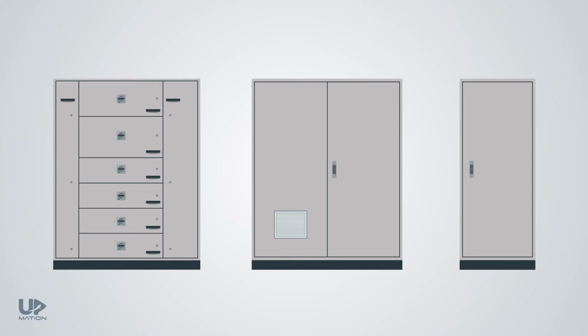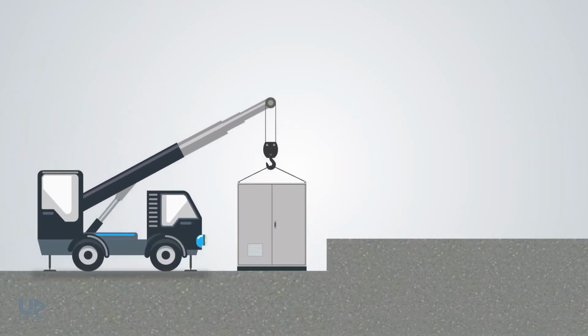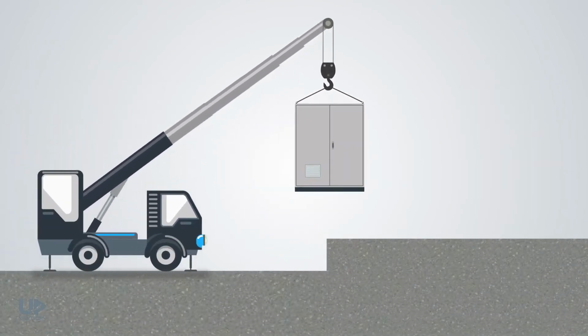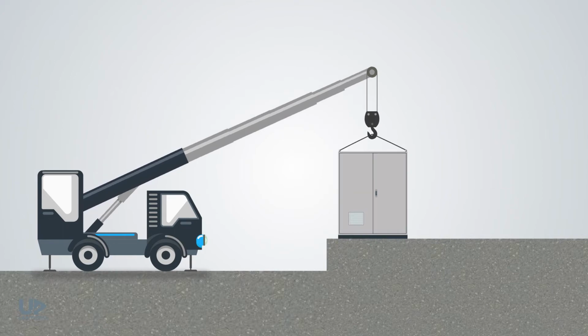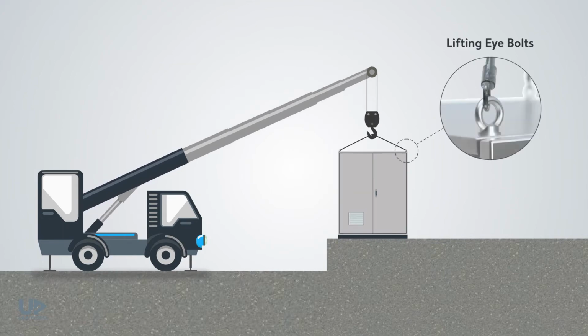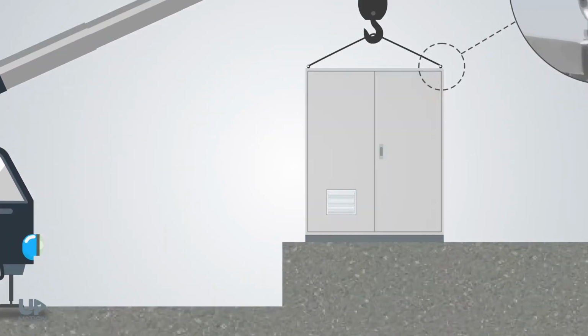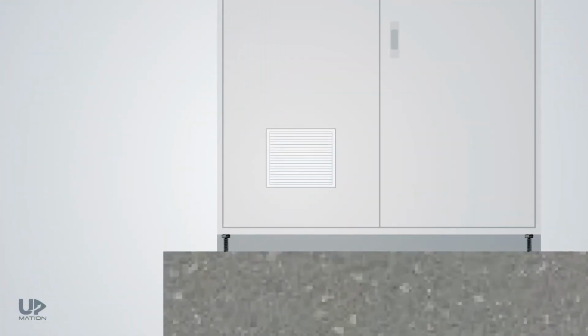As all of the electrical panels have a metal enclosure accommodating many electrical and non-electrical devices, they are pretty heavy most of the time. Therefore, to lift, move, or install them using a crane, the enclosure manufacturers consider lifting eyebolts directly on top of the frame corners. After the placement of the panel in its final position, we should fix them there by bolting their bottom frames to the ground.